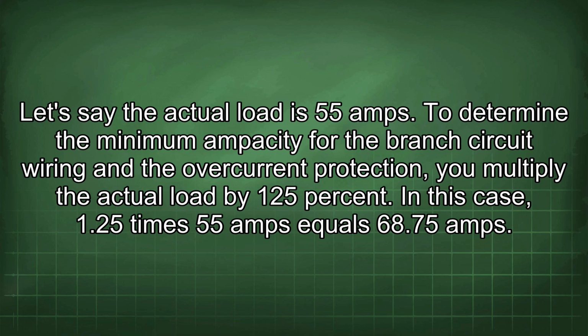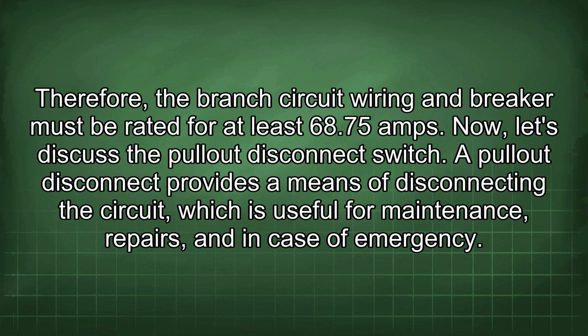To determine the minimum ampacity for the branch circuit wiring and the overcurrent protection, you multiply the actual load by 125%. In this case, 1.25 times 55 amps equals 68.75 amps. Therefore, the branch circuit wiring and breaker must be rated for at least 68.75 amps.